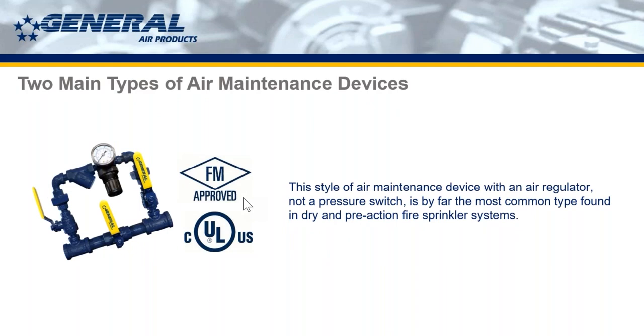So going back to now the AMD1, or air maintenance device AMD1, without the pressure switch, it has a pressure regulator. This style of device, with the regulator, not the pressure switch, is by far the most common. That's because there's very small amounts of compressors that are sold in the fire sprinkler market anymore that do not have a pressure switch already included with them. So really, the AMD1 is the one you should be dealing with all the time.